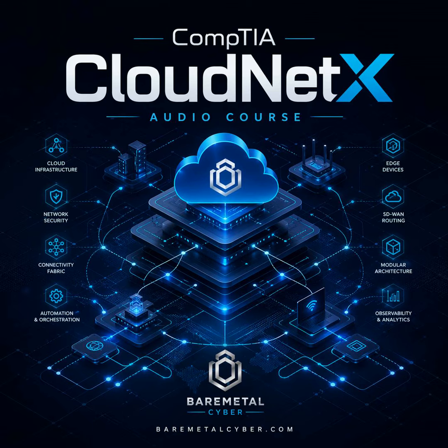In episode 59, titled Environmental Requirements, Temperature, Humidity, BTUs, and Failure Prevention, the focus is on environment as a slow risk that can quietly build for weeks and then present as a sudden, ugly failure at exactly the wrong time. Environmental control is easy to deprioritize because it feels like facilities work, yet it directly determines the reliability of network and compute gear. The exam tests this topic because environmental problems often masquerade as random technical faults, and because basic concepts like heat load and humidity thresholds are foundational to uptime.